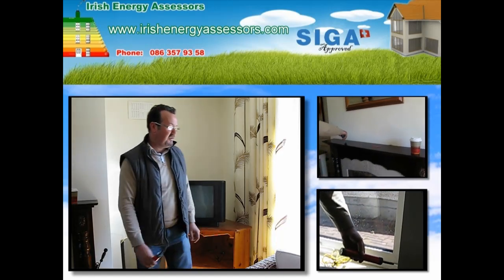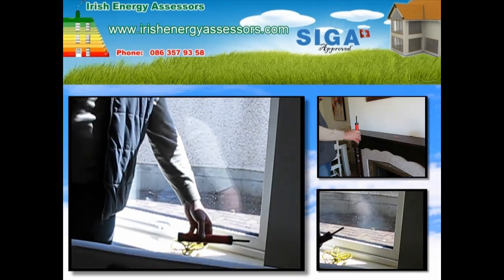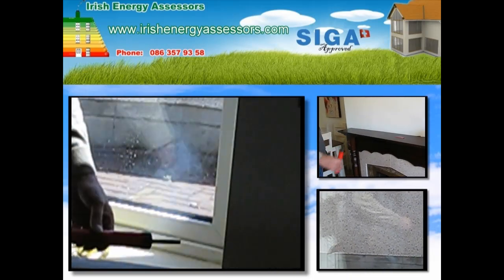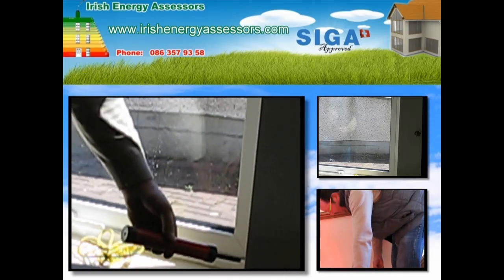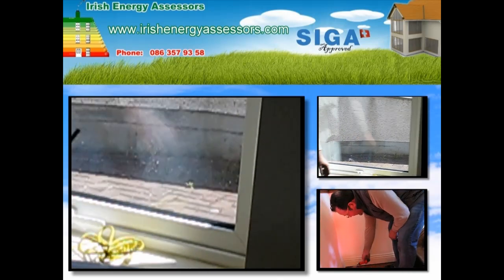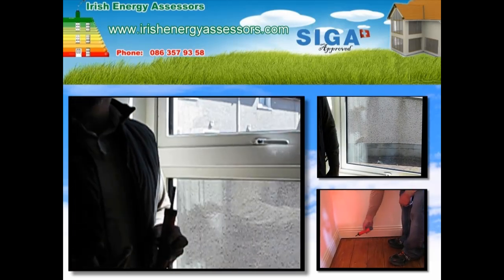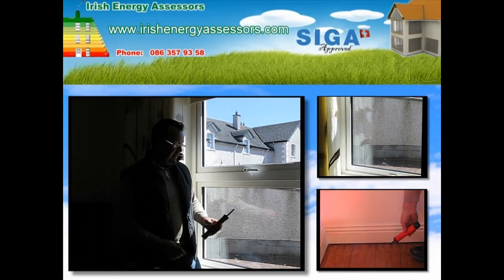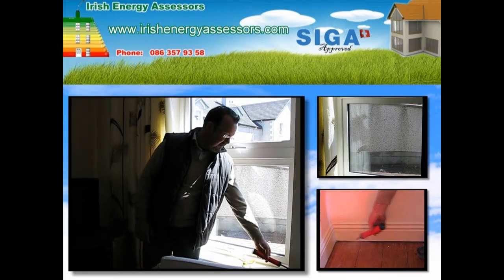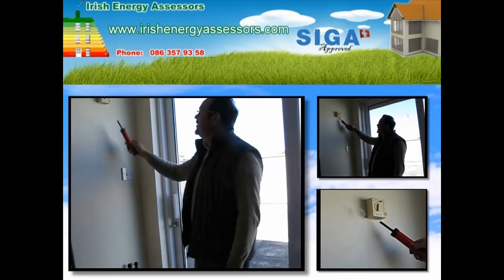We're going to concentrate here on the corner of this window. It just shows you how much heat is leaving this house. See the smoke? It's being actually blown back from the window. This is caused by the depressurisation of the fan.